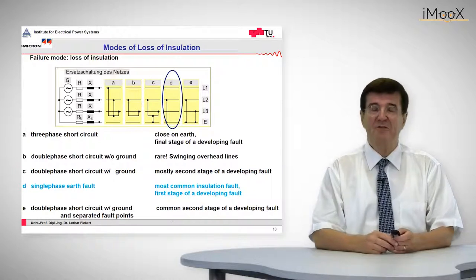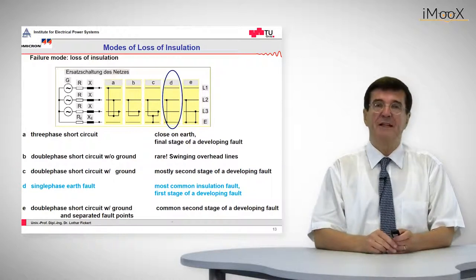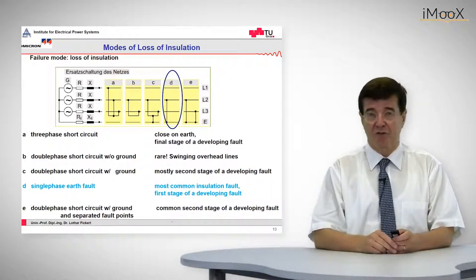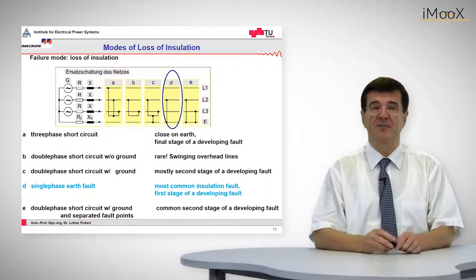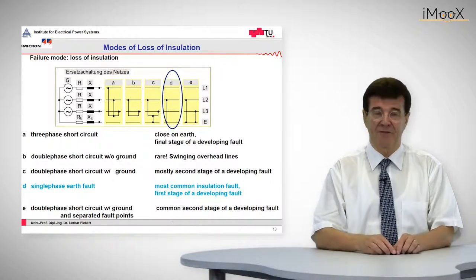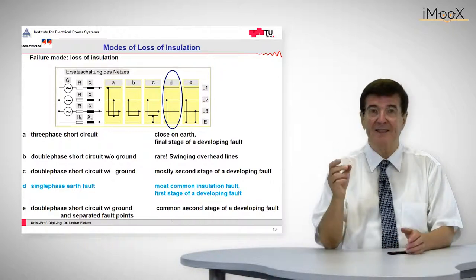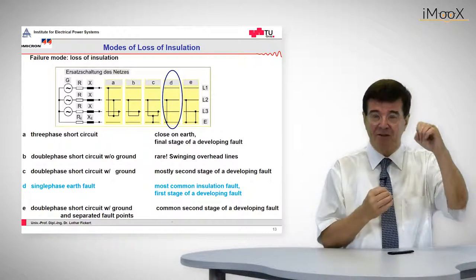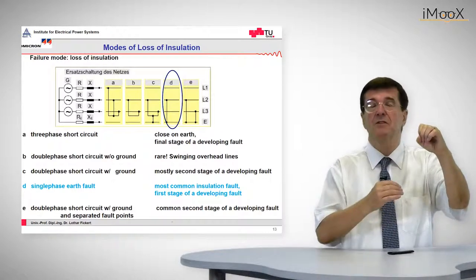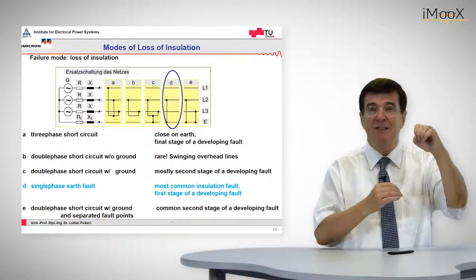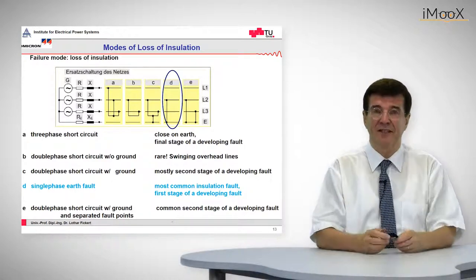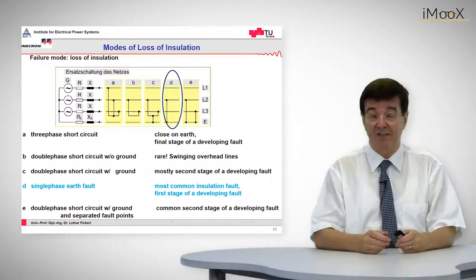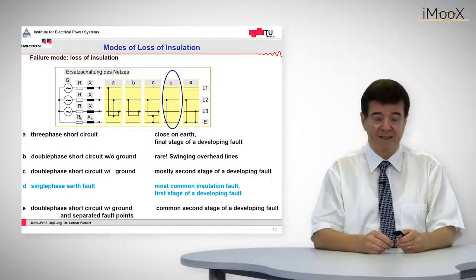The single-phase to ground fault, as I mentioned before, is the most common one because it is caused by the breakdown of insulation. Breakdown of insulation means we have a field between the hot conductor and the cold ground, and if this insulation does not sustain this field anymore, then we have an insulation breakdown — a fault between phase and ground.